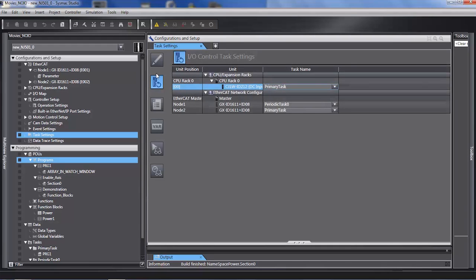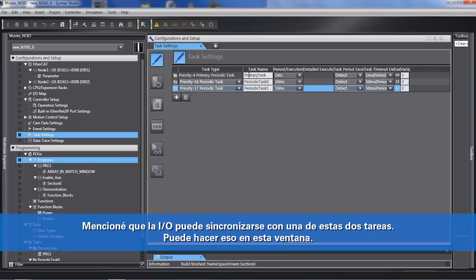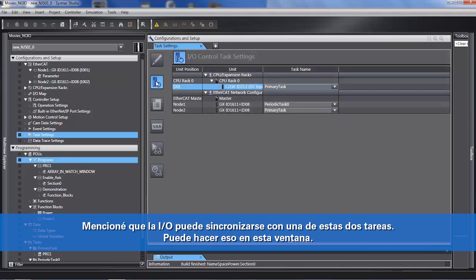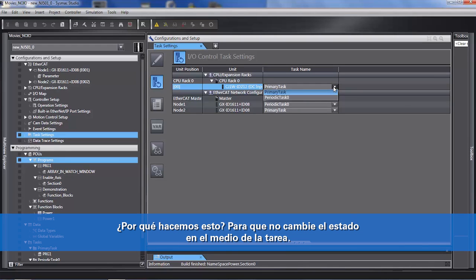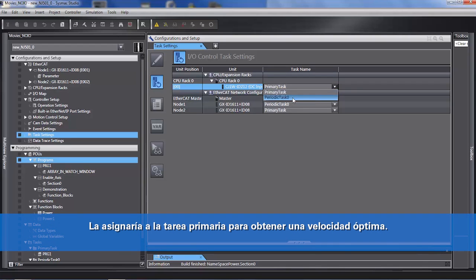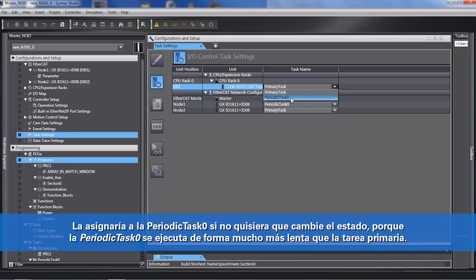In the second window, I mentioned that the IO can be synchronized to one of these two tasks. You do that in this window. Each input card and output card on the local rack or IO system can be synchronized to either one of the tasks. We do this so that IO does not change state in the middle of a task. You would assign it to the primary task to get optimum speed, or assign it to periodic task zero if you didn't want it to change state, since periodic task zero runs much slower than the primary task.